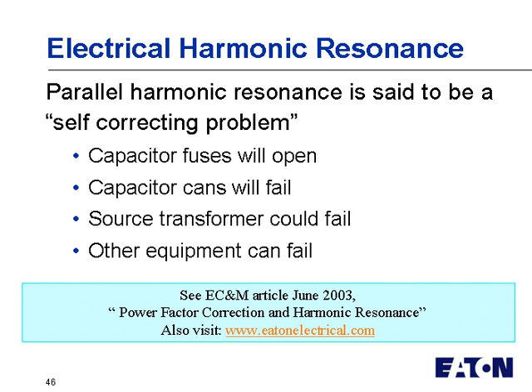Electrical harmonic resonance, unfortunately, is said to be a self-correcting problem, and typically the way that you see it manifest itself is capacitor fuses will fail or open. Capacitor cans may actually fail, or other system equipment could fail. And there's an article that I put together in EC&M magazine, and we also posted on our website about power factor correction and harmonic resonance if you're interested and you want to look further into that.